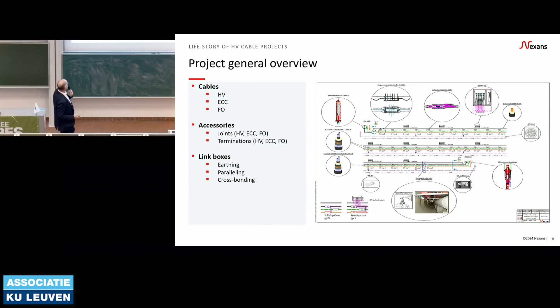Then you need a layout. It's good to have your cable, but what do you do with it? The layout of your link requires information about the cables, the accessories, the link boxes for the cross-bonding of the screens or the earthing of the electrical continuity conductors. Then you need additional points, like if you have optical fibers, you will have some optical fiber racks or things like that. You need special support, special techniques to install the cables in tunnels and so forth. The first point is to have your image of the link to know what is at stake.